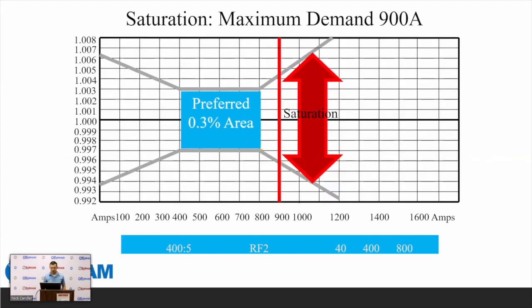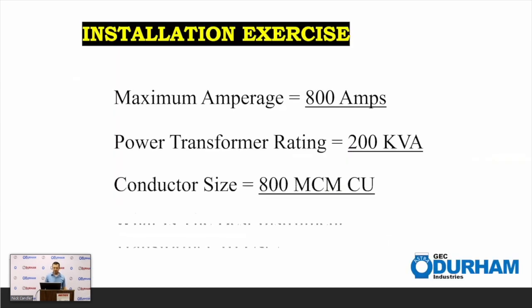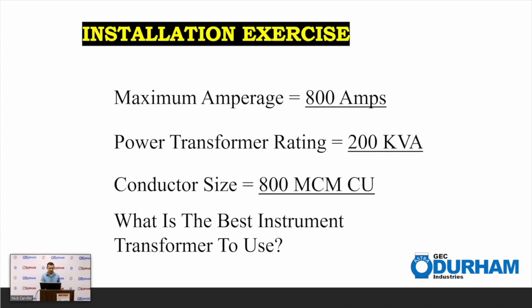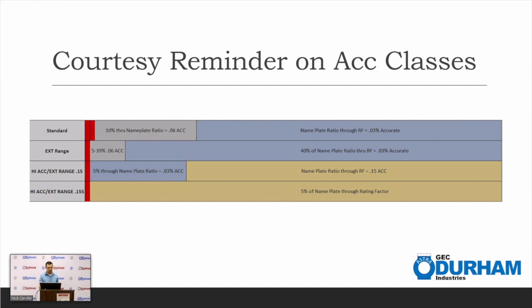So again, saturation. You put a 400 to 5 transformer into service, and the customer demands 900 amps. Well, your utility is not going to generate much revenue beyond that 800 amps. The CT is going to go into saturation, and the utility is going to lose some money. So you want to make sure you size these accurately. Speaking of which, let's take a look at an 800 amp service, and let's pick a ratio that might work best for this 800 amps. And again, just a reminder, we want to size according to the rating factor, but we also want to consider the nameplate ratio, because this ideal accuracy range is limited.